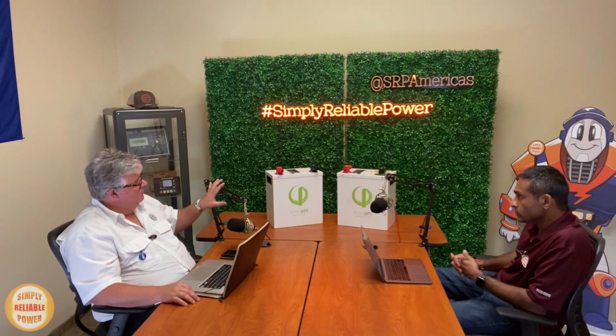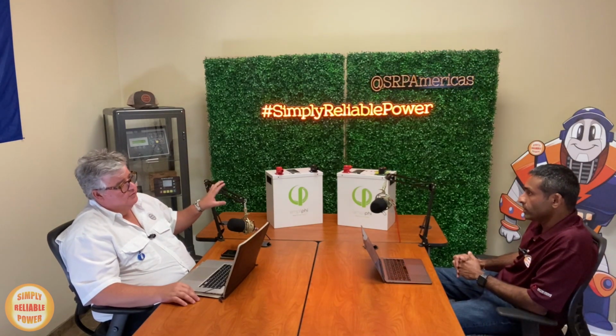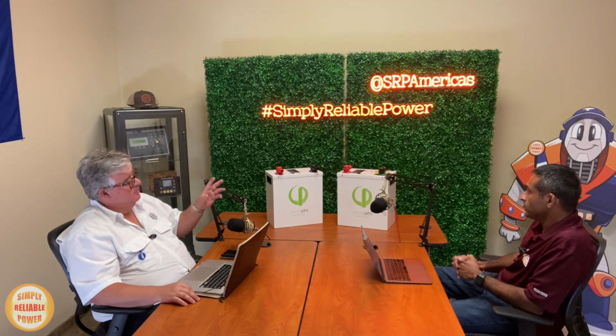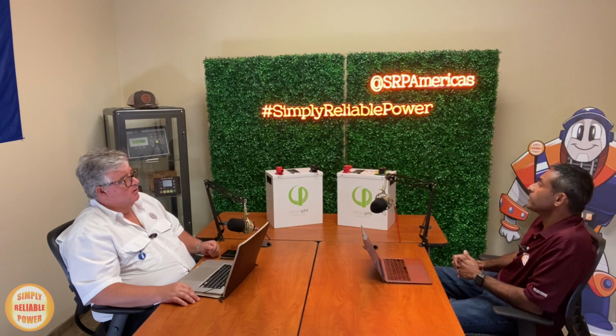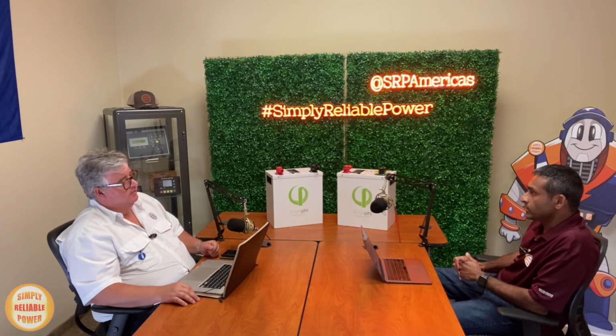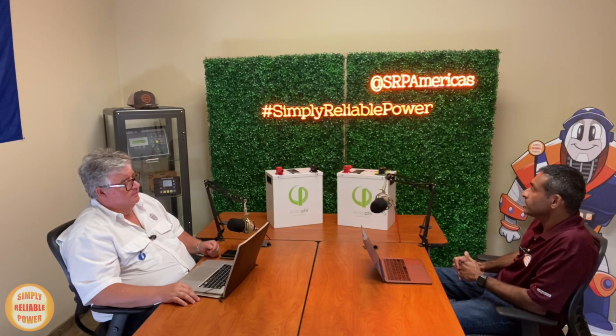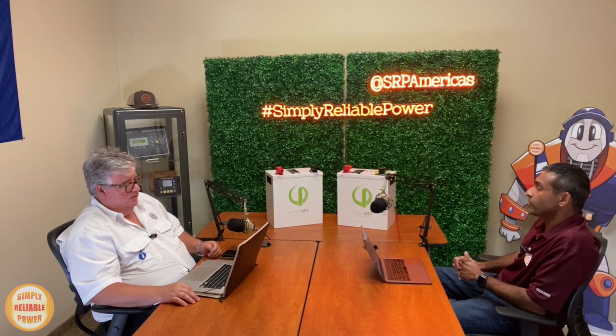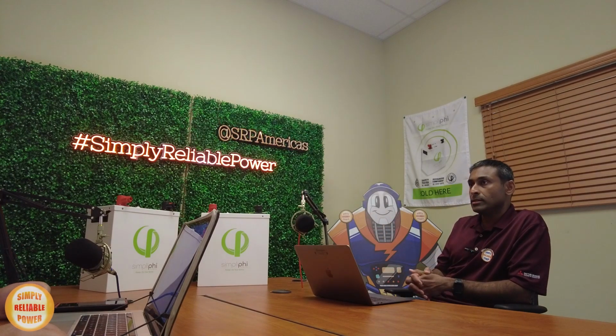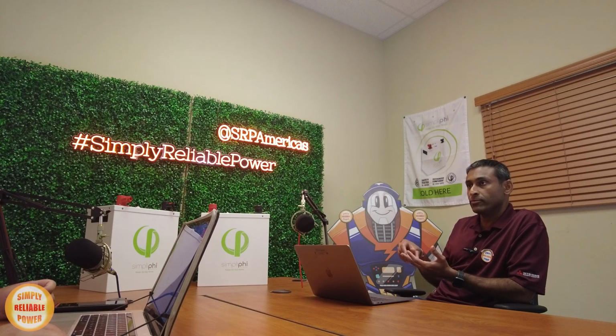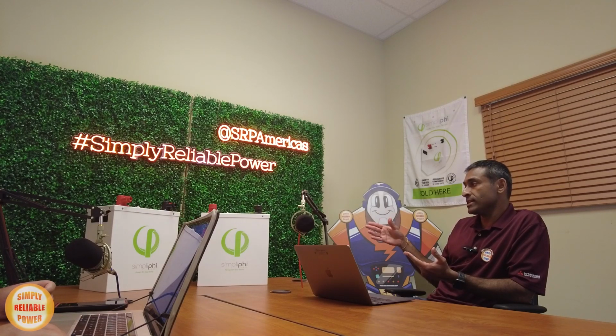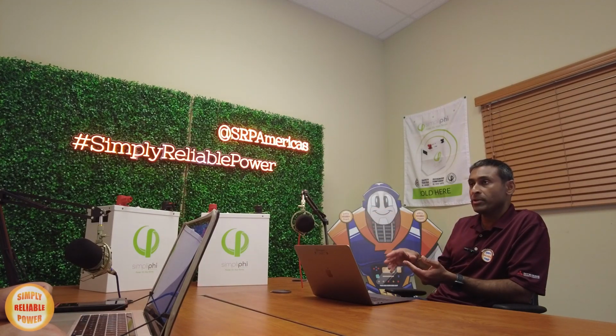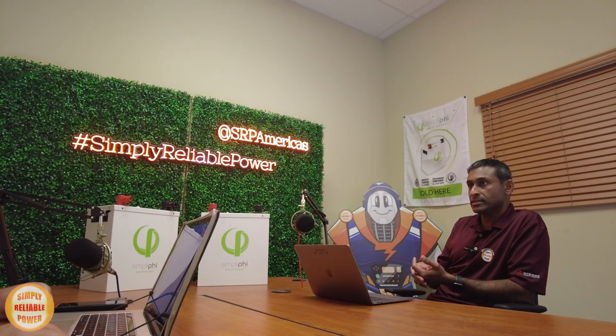Okay, so if I understand correctly, the PHI battery's BMS is really just working as a protection for the individual battery. That's right. In the case of the AMPLIPHI battery, it's doing a lot more. That's right. It's talking to other batteries, it's talking to inverters, and optimizing itself for better performance. Better performance and providing information to the inverter, such as state of charge, the exact battery voltage, and the charge and discharge rates that battery is capable of giving out based on the temperatures and all the other conditions of the battery.